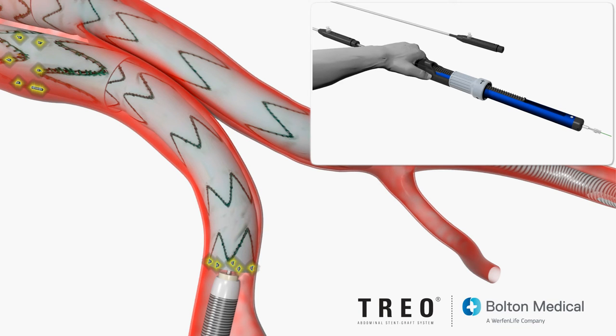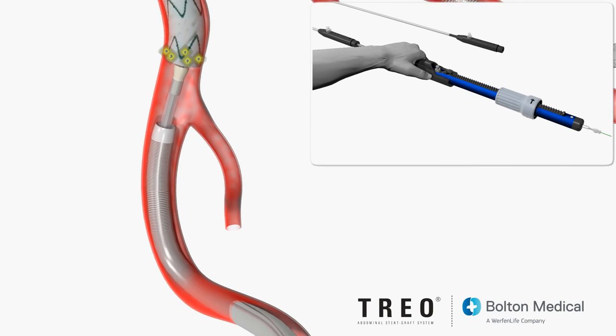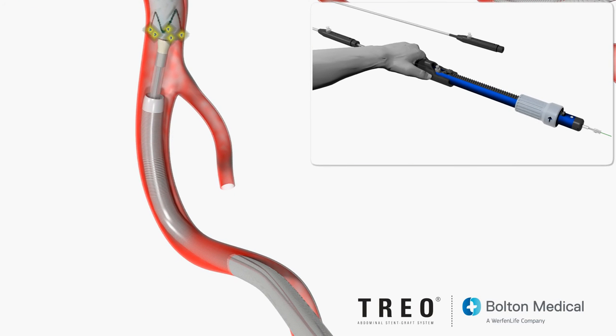Completely retract the leg extension sheath until the leg extension stent graft is completely deployed. Observe the distal markers on the leg extension to ensure the sheath clears both.